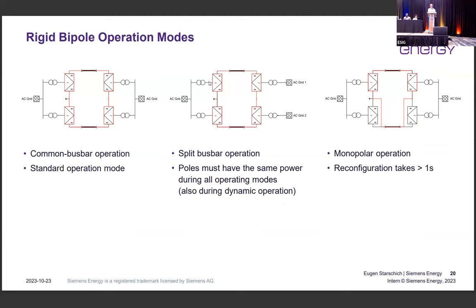Here, in this reconfiguration coming from this operation mode to this one, it takes more than 1 second, because there are a few mechanical DC switches that need to be operated. This is something to take into account in the configuration of the network stability. With the rigid bipolar, you have less redundancy, and the reconfiguration in case of a fault takes more than 1 second.